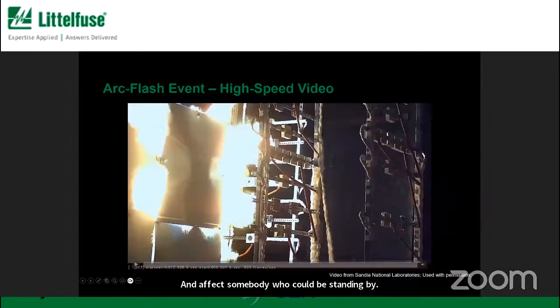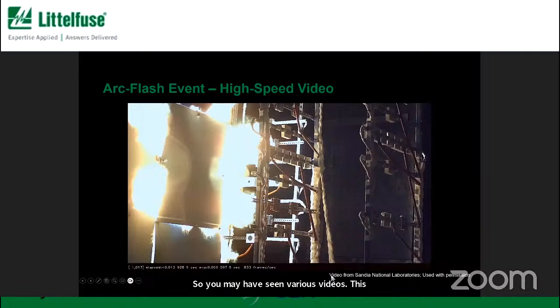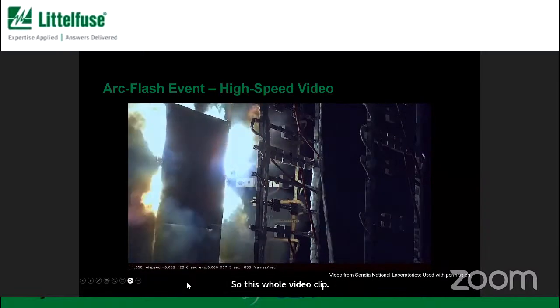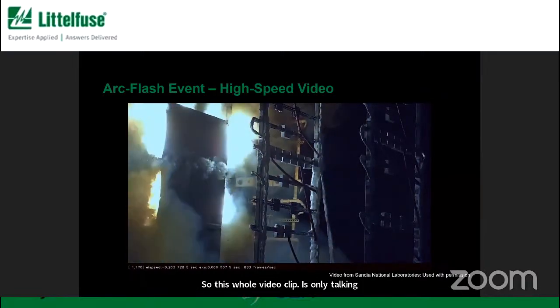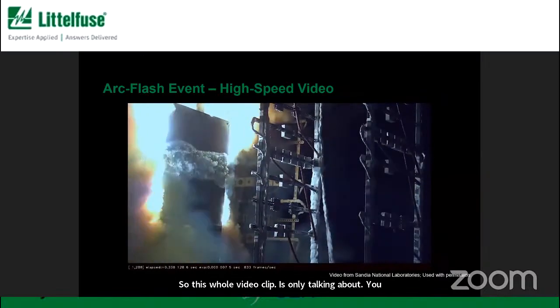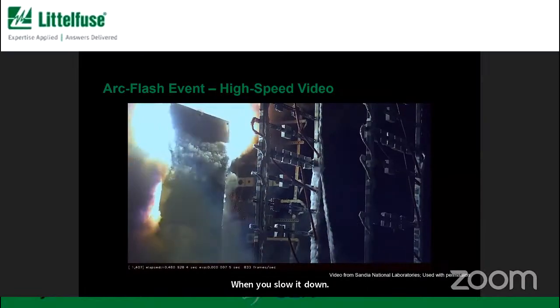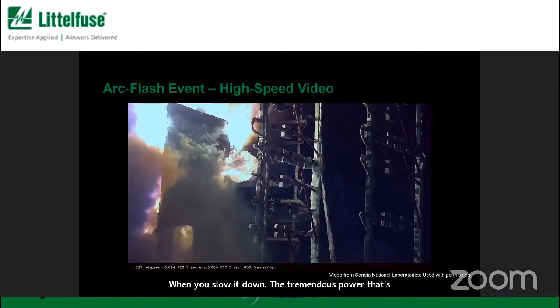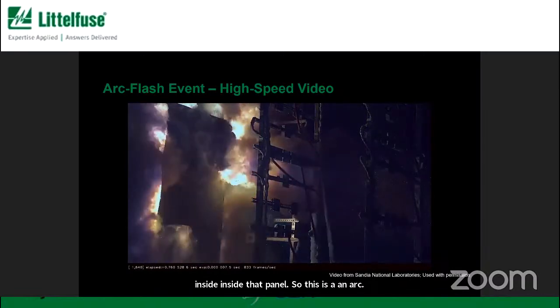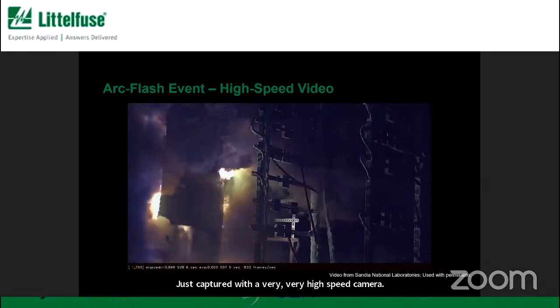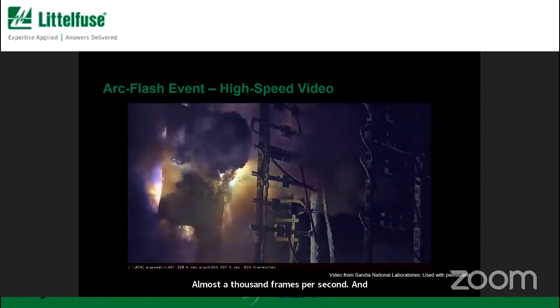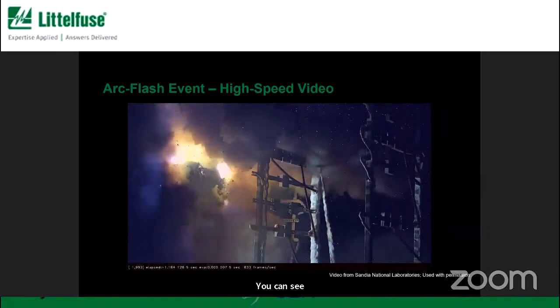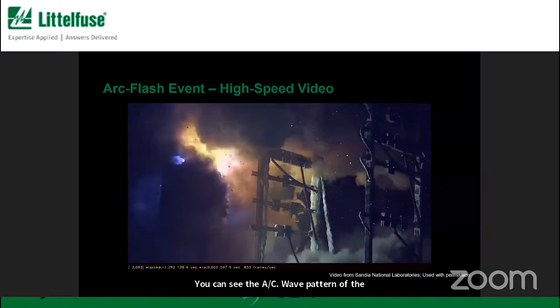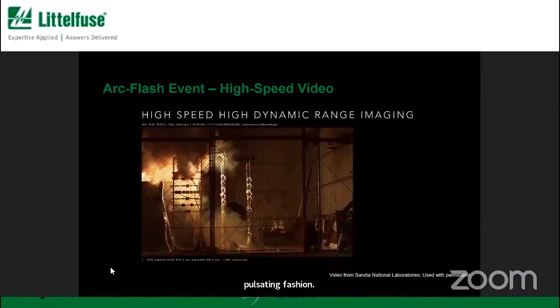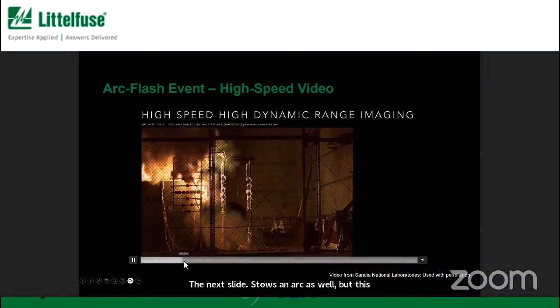So you may have seen various videos. This is just one that I like because it's in very slow motion. This whole video clip is only talking about a few milliseconds, but you can see when you slow it down the tremendous power that's inside that panel. This is an arc captured with a very high speed camera, almost 1,000 frames per second, and you can see the AC wave pattern of the arc in that pulsating fashion.